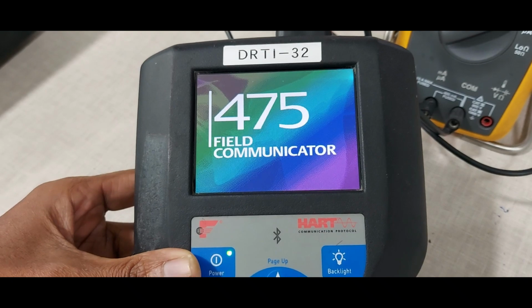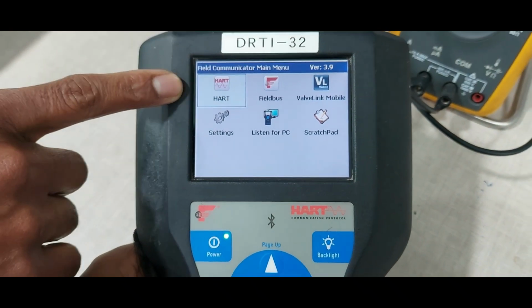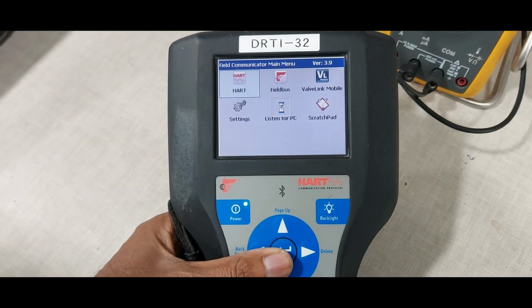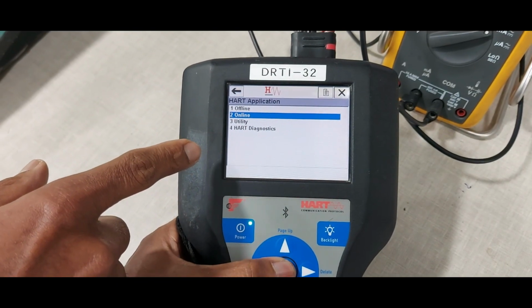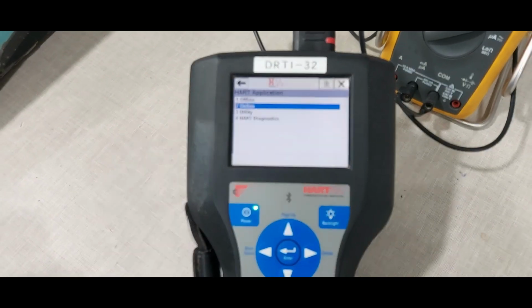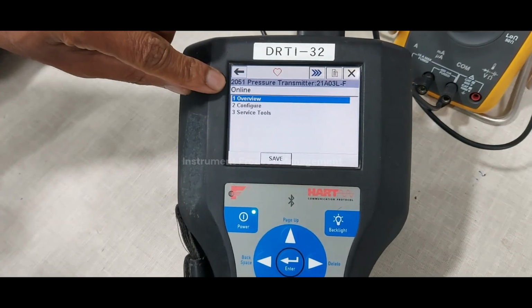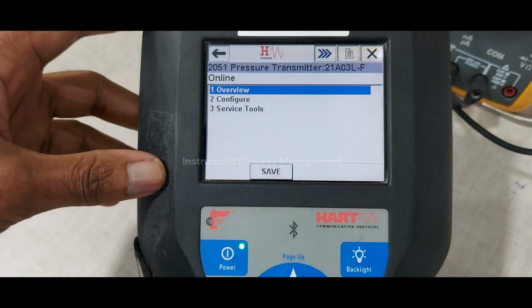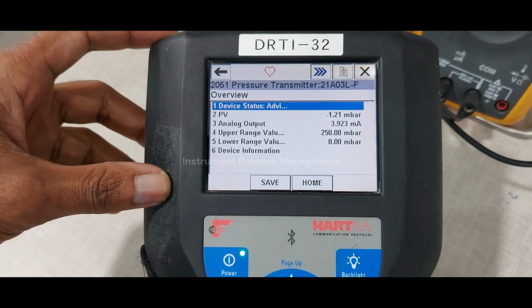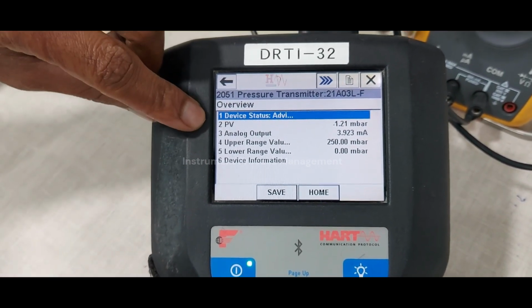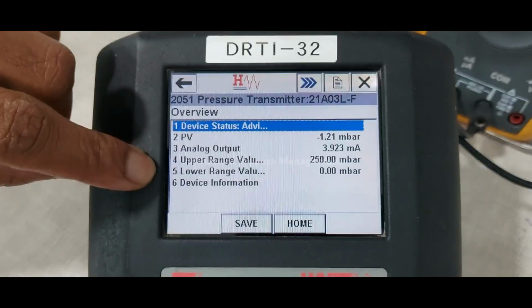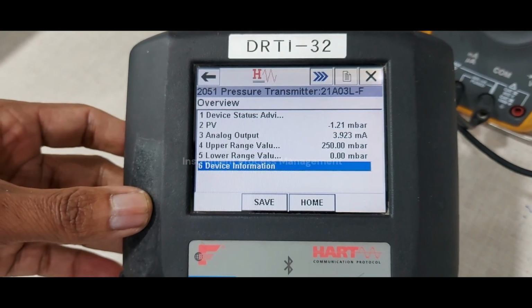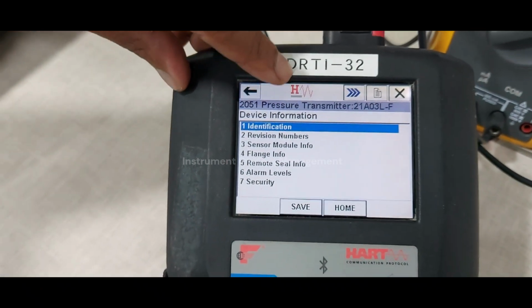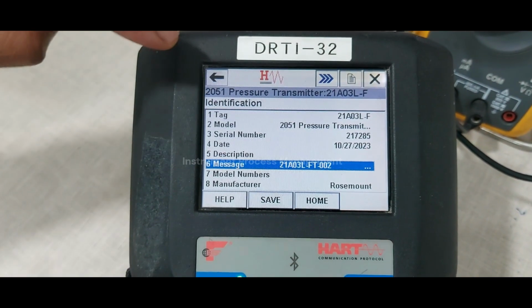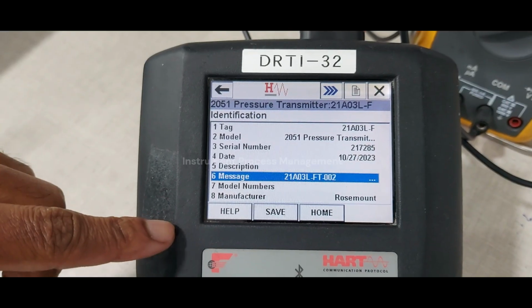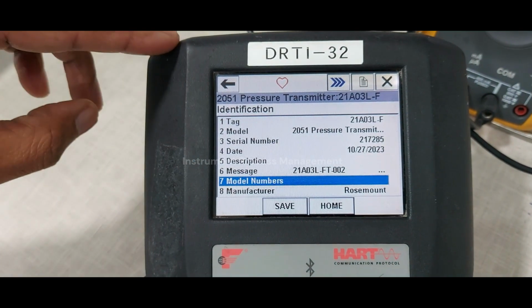Power on the communicator. Select the HART interface. Select the online menu. Online menu showing overview, parameters, configuration and service tools. First we are checking the overview condition. The device status, PV, analog output, upper range value and lower range value, device information. Device information, I will open it. Okay, identification number, we can add the identification number in this area. Long tag already assigned, description not assigned, unit model number also we can add it from this area. Unit serial number also there.